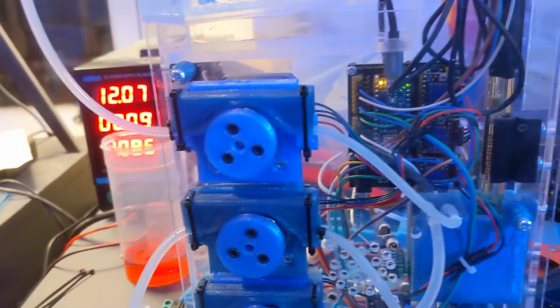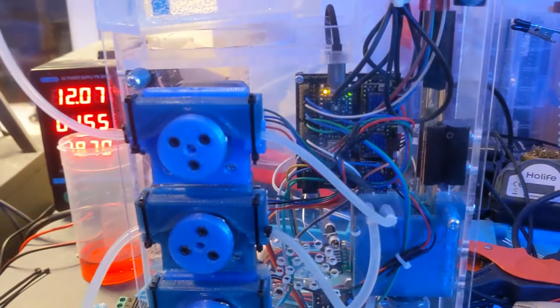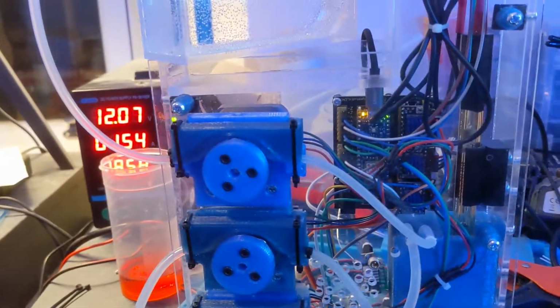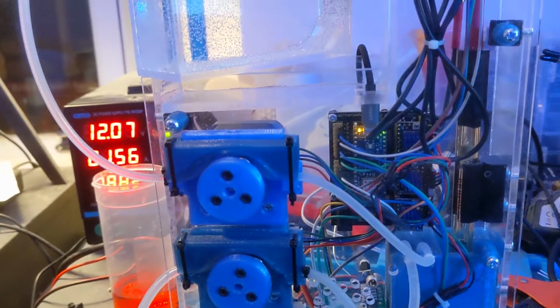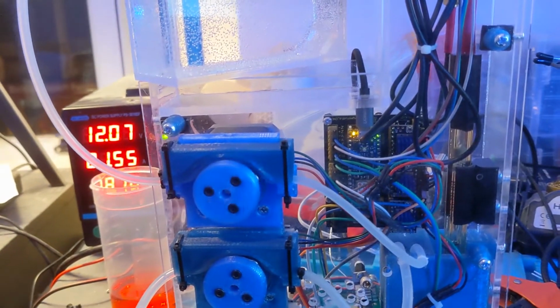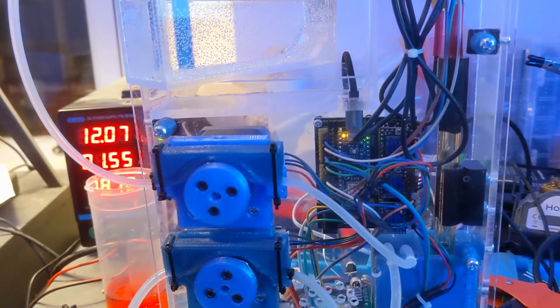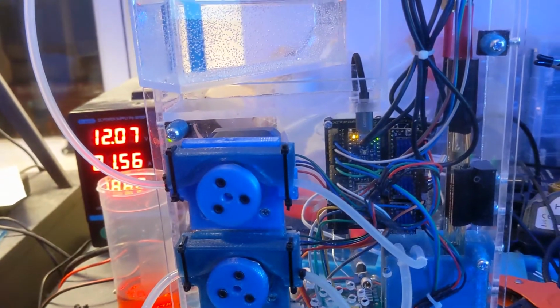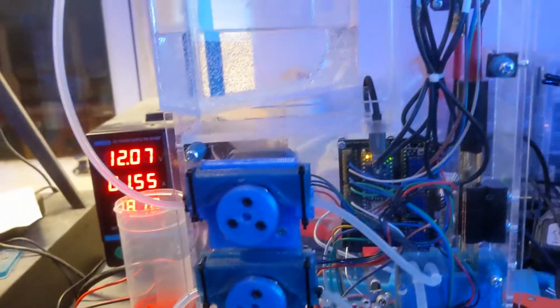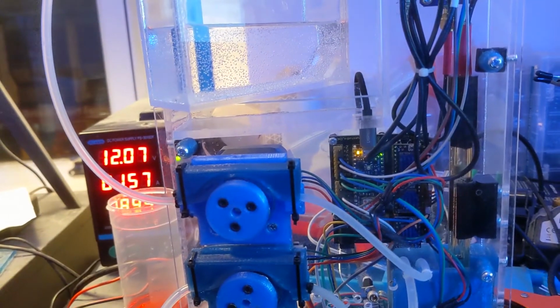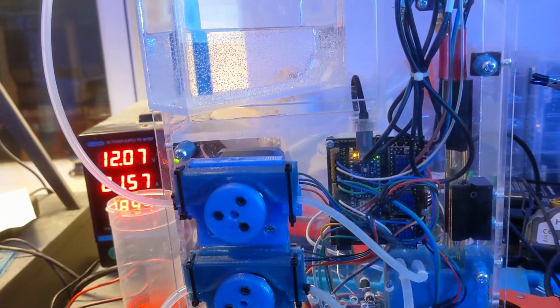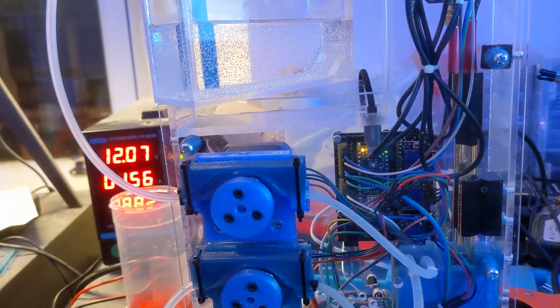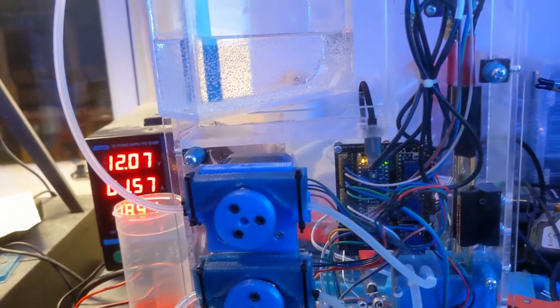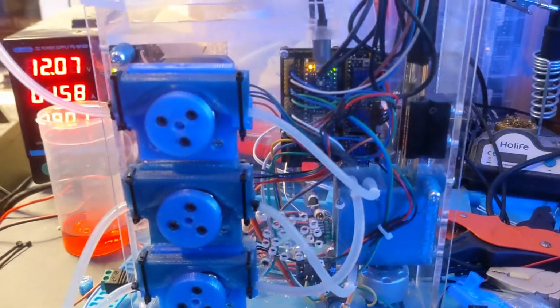And what it's doing right now, it's in the middle stage at the moment. It's got 3 stages of titration. It's got a fast, a medium, and a slow stage. So in the fast stage, it adds 0.3 milliliters at a time, and checks the pH. And if the pH is dropping very, very rapidly, then it skips a dose. If it's dropping by a more reasonable amount, then it will immediately do the next dose after it's had a few seconds to stir.